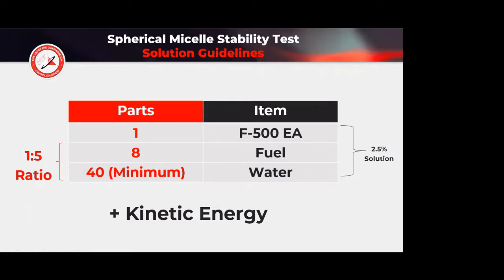If you sprayed water down, the fuel is lighter than water. It's going to float on the top, so we all know that. You could put foam down, but a foam blanket will dissipate. You'll have to apply foam a second time or even a third time. And you can't do it with a wetting agent because a wetting agent doesn't encapsulate.